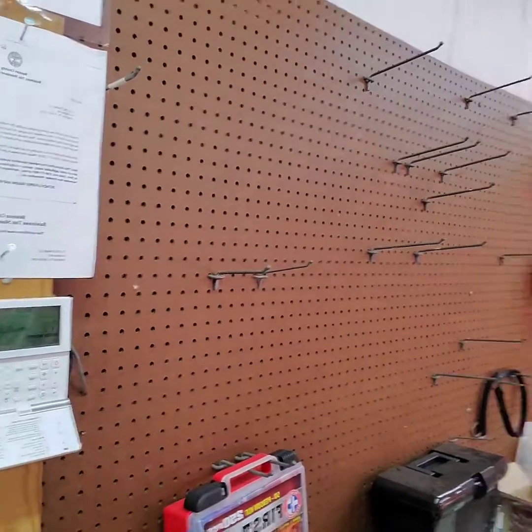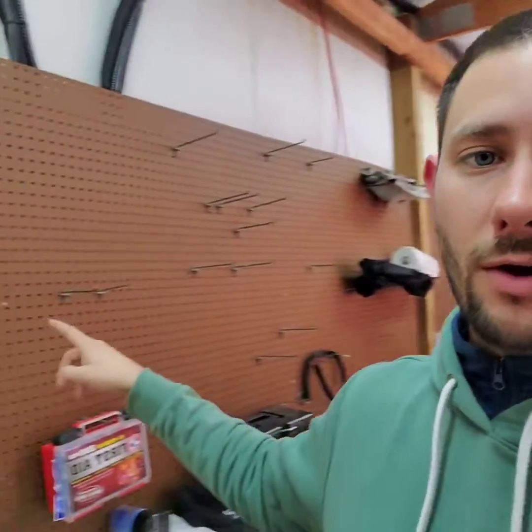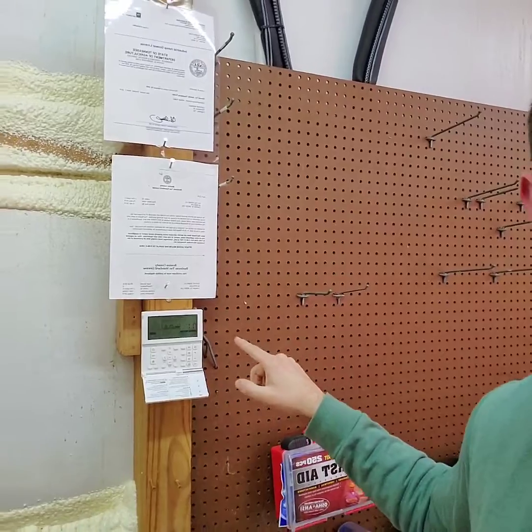I'm going to show you how to get to temperature sensor selection and make the setting so you can choose between using this wired remote controller as the temperature sensor, or the actual sensor in the unit. What does this do? If the wired remote controller is in a location where it's not actually getting the heat from the unit or the space, it won't overheat. If we need it to run off the sensor in the unit to better acclimate the area and not overshoot the heating setting, we'll change the temperature sensor selection to the indoor unit.